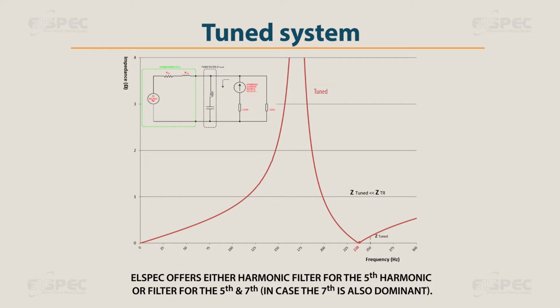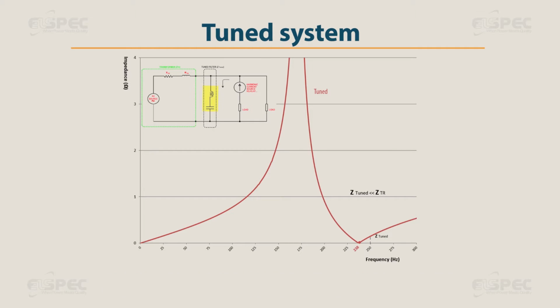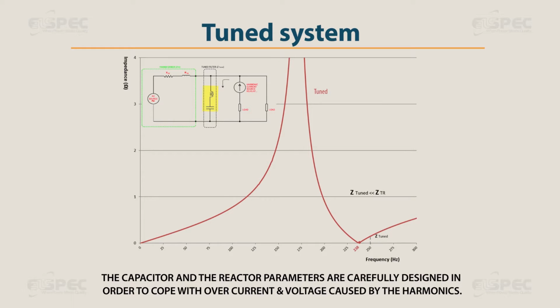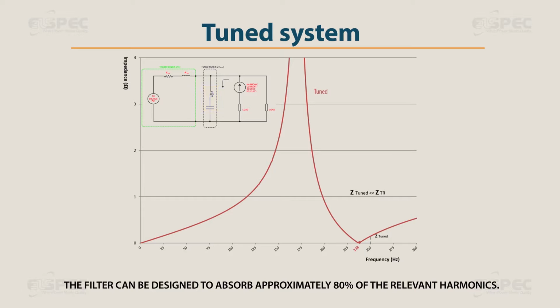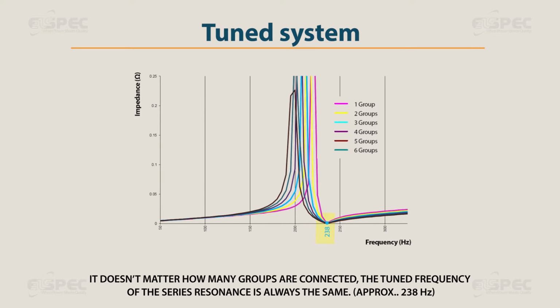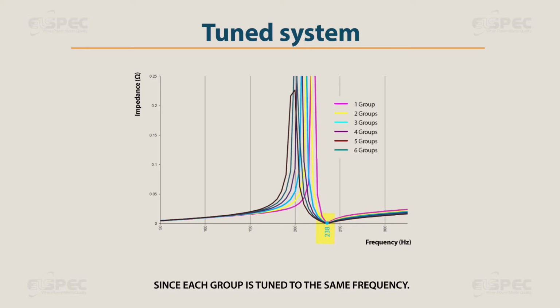ELSPEC offers either a harmonic filter for the 5th harmonic, or a filter for the 5th and 7th in case the 7th is also dominant. The capacitor and reactor parameters are carefully designed in order to cope with the overcurrent and voltage caused by the harmonics. The filter can be designed to absorb approximately 80% of the relevant harmonics. It doesn't matter how many groups are connected. The tuned frequency of the series resonance is always the same, approximately 238 Hz, since each group is tuned to the same frequency.